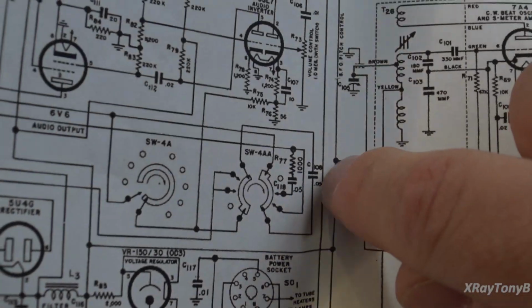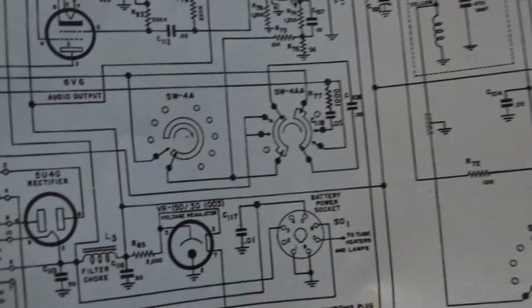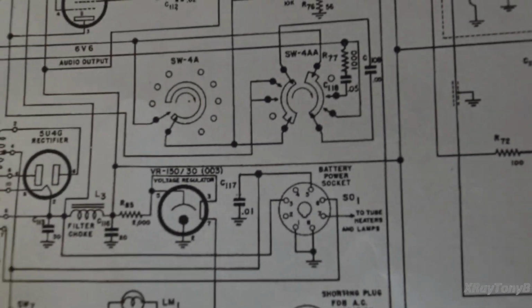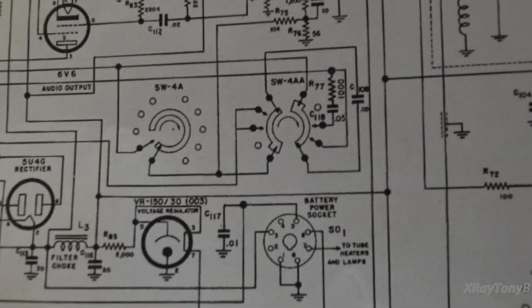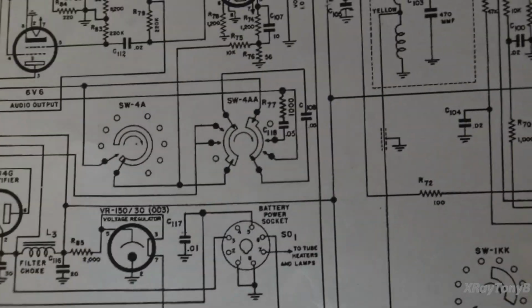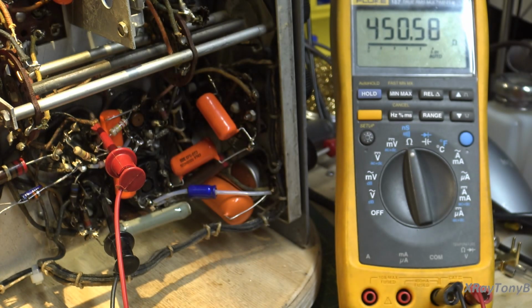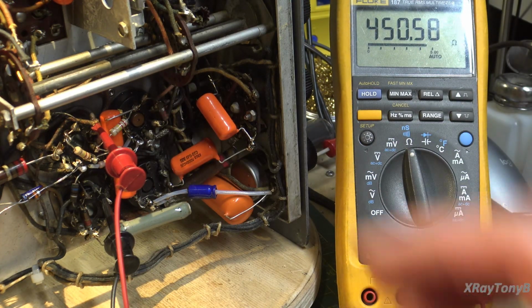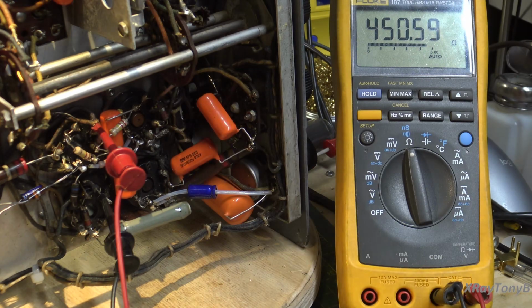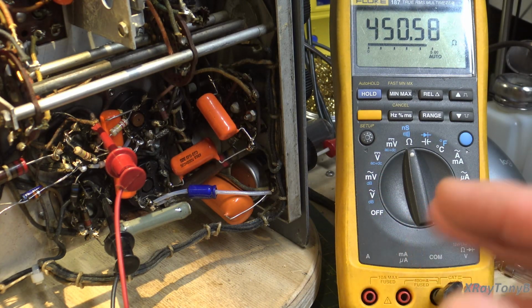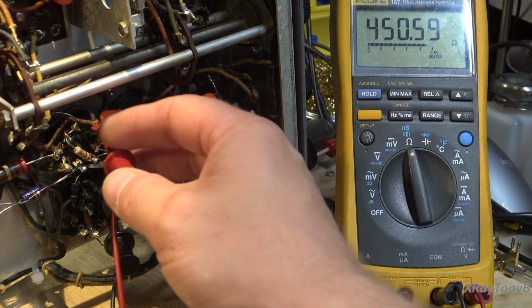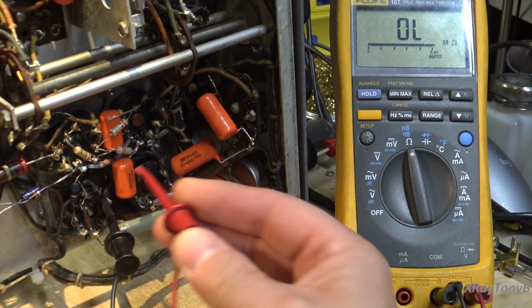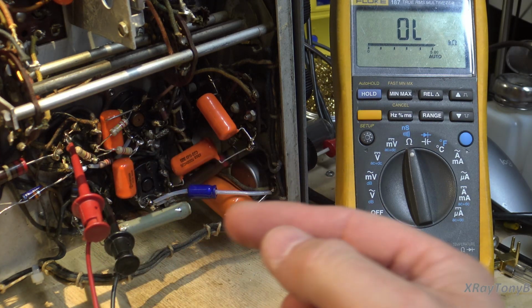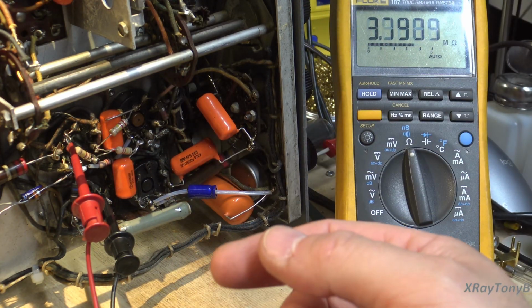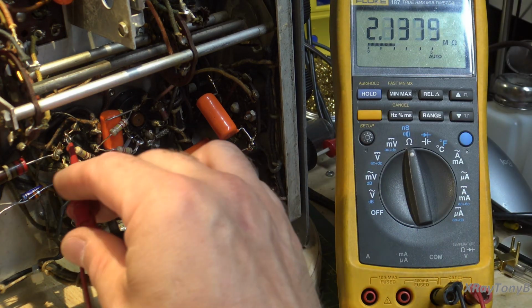And what happens is these capacitors are notorious for developing resistance and eventually shorting out, and when they short, they will actually damage that transformer. This still doesn't mean the transformer is not damaged, but at least we know we don't have a short between those windings there. And if I measure with reference to ground, which this pin is grounded, I'm not seeing anything there either - we're just reading through a capacitor.